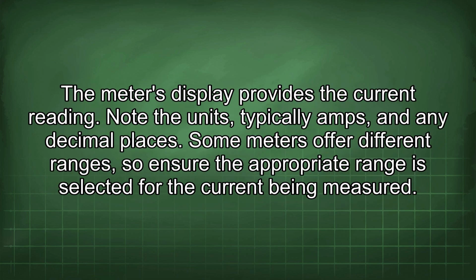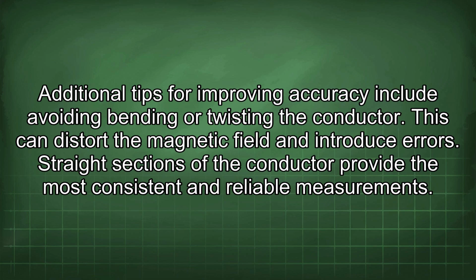The meter's display provides the current reading. Note the units, typically amps, and any decimal places. Some meters offer different ranges, so ensure the appropriate range is selected for the current being measured. Additional tips for improving accuracy include avoiding bending or twisting the conductor. This can distort the magnetic field and introduce errors. Straight sections of the conductor provide the most consistent and reliable measurements.